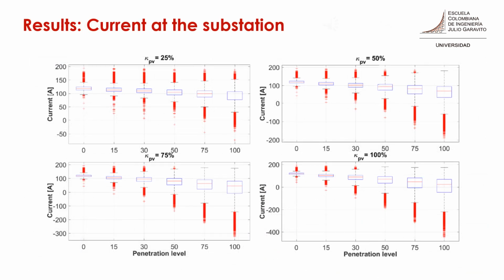After performing the simulations, the results can be analyzed. The current in the feeder behaves similarly to the active power. When the penetration level increases, the current decreases. However, at some point, the reverse current increases. The results indicate that starting from 30% of PV penetration, there is a latent probability of reverse power flow. Therefore, if reverse power flow at the substation is not allowed, a PV hosting capacity of 30% can be established for the studied distribution system.